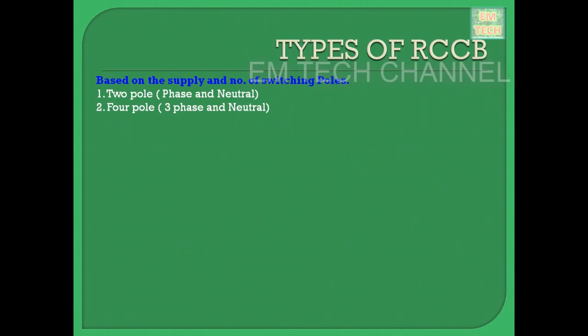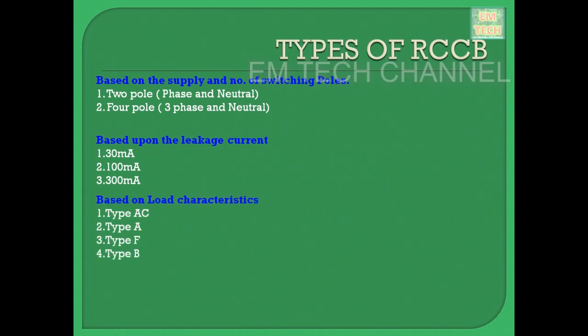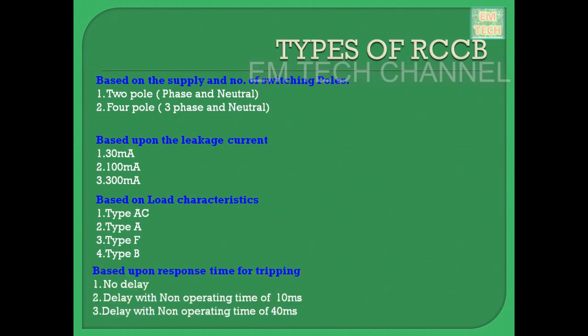Next, it is classified based upon the leakage current. RCCB comes in 3 major ratings: 30 milliamps, 100 milliamps and 300 milliamps. Next, based on the load characteristics, RCCB comes in 4 major types: type AC, type A, type F and type B. And finally, based on the response time for tripping, that is the delay from finding the fault to tripping the circuit, it comes in 3 variants: no delay, delay with a non-operating time of 10 milliseconds, and selective delay with a non-operating time of 40 milliseconds. The second and third types are used where nuisance tripping is not permitted.